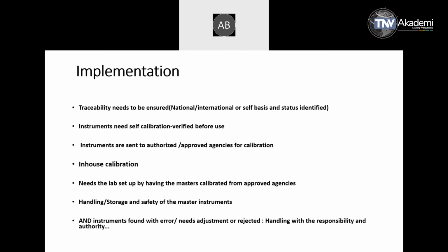So we are now into the implementation of the measurement systems and calibration systems. Traceability needs to be ensured. As I was discussing earlier, national traceability or international traceability, or at times there are no national or international standards available for particular items or processes. At that time the organization will develop its own self-developed traceability and inspection method, and will naturally document it and keep on monitoring it.